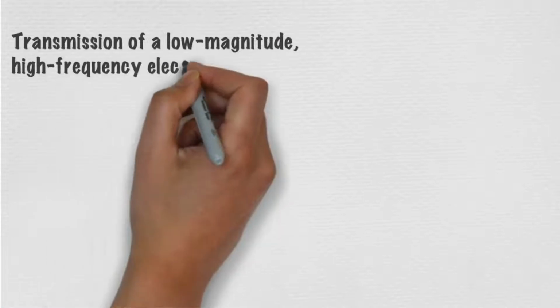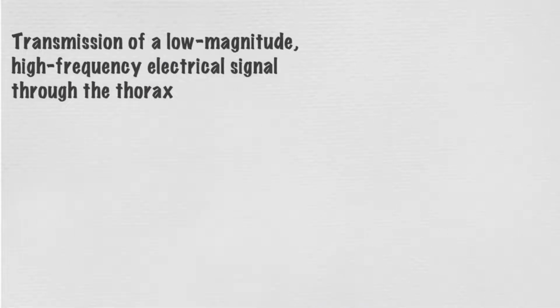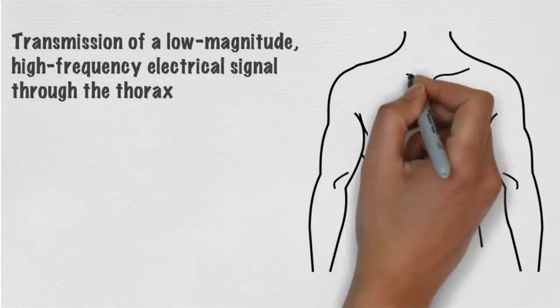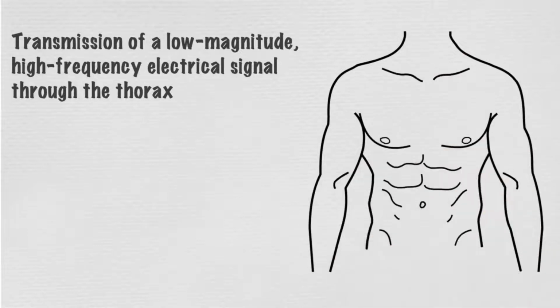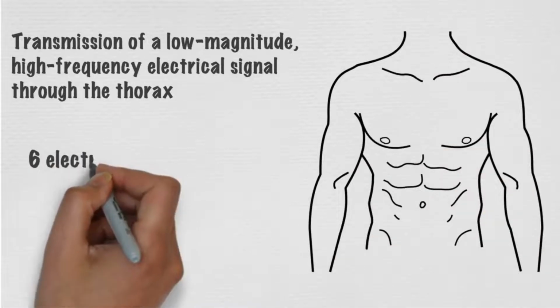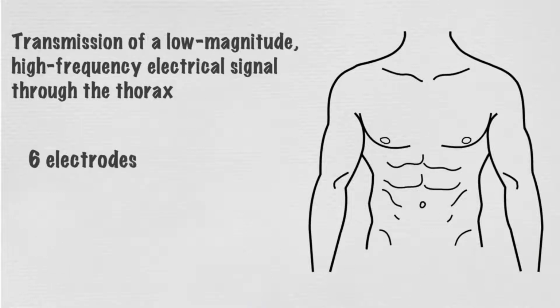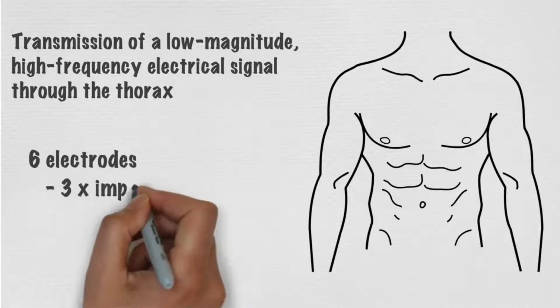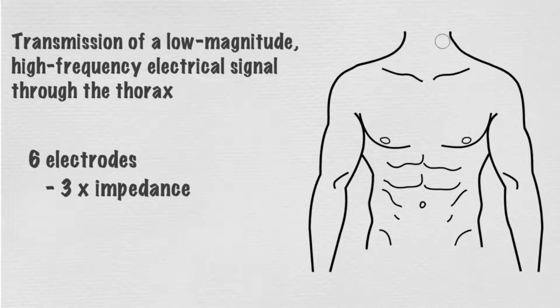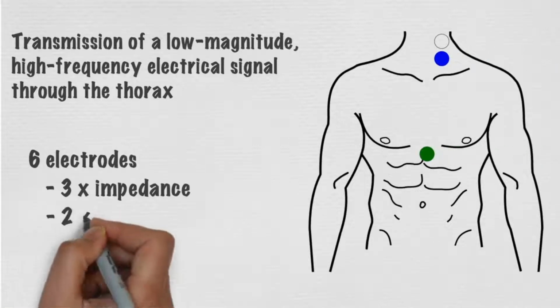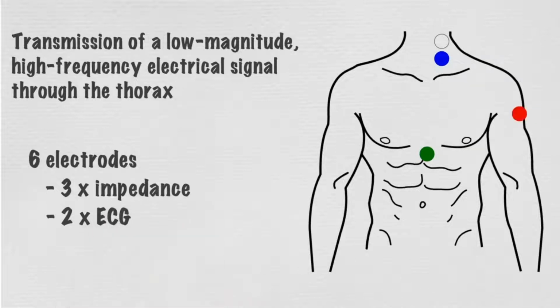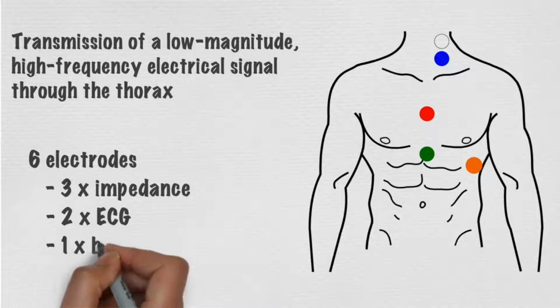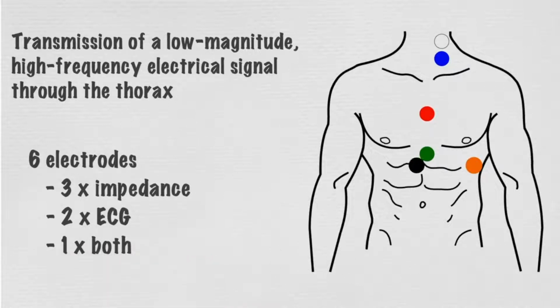HD-ICG is a completely non-invasive technology and measures stroke volume via the transmission of a low-magnitude, high-frequency electrical signal through the thorax. 6 electrodes are applied to the neck and the torso. 3 of these, the white, the blue, and the green, are impedance electrodes. 2 of them, the red and the orange, are ECG electrodes. And 1, the black, is both an impedance and ECG electrode.